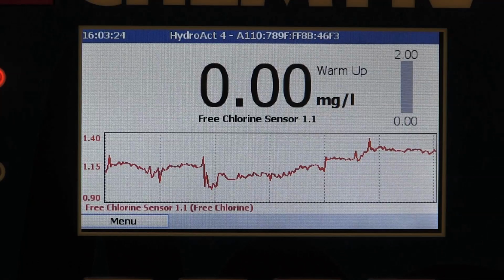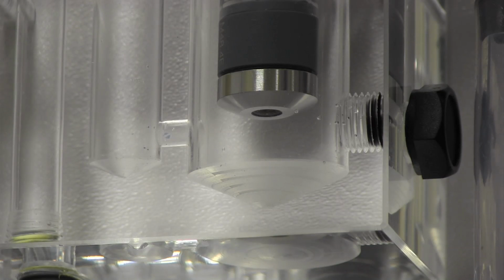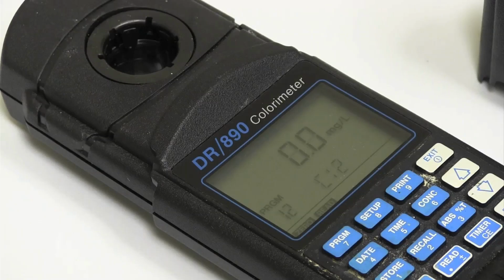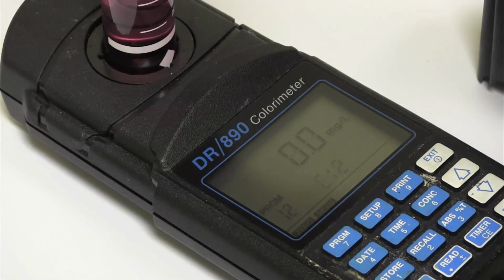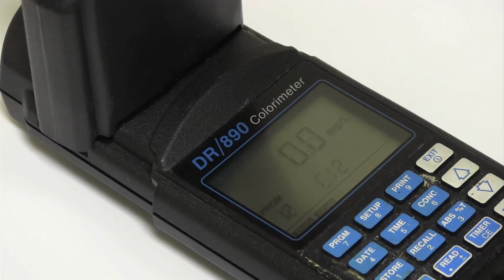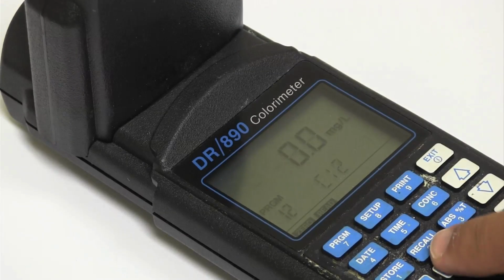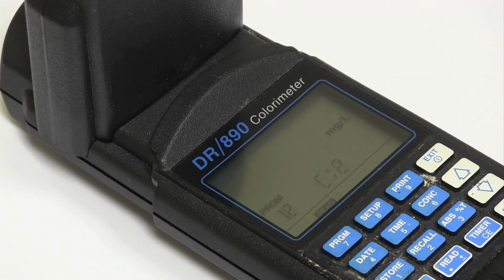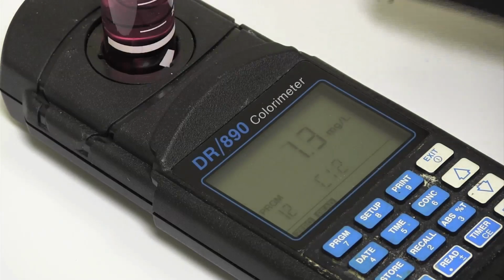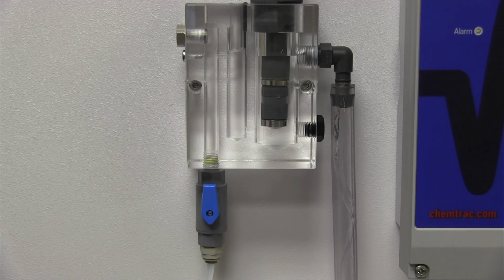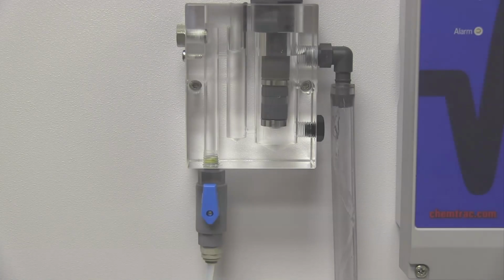When the probe is initially connected to the analyzer, the display will indicate that it's in a warm-up phase. The warm-up and stabilization period should be a minimum of 2 hours, and during this time, the sample flow must have a chlorine concentration that is greater than 10% of the range of the probe. So for a 0 to 5 ppm probe, there should be at least 0.5 ppm chlorine in the water. Following the 2-hour warm-up period, a calibration can be performed.